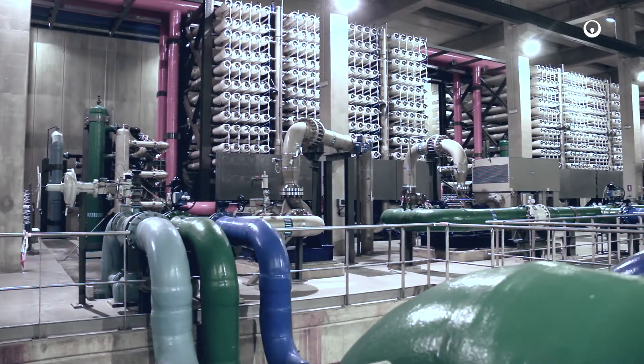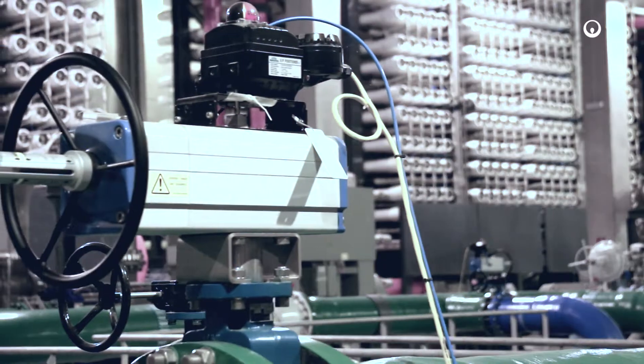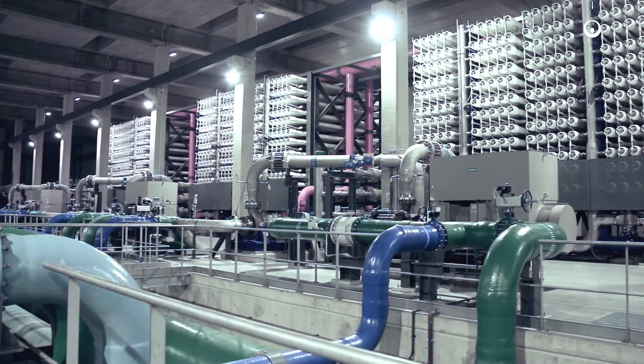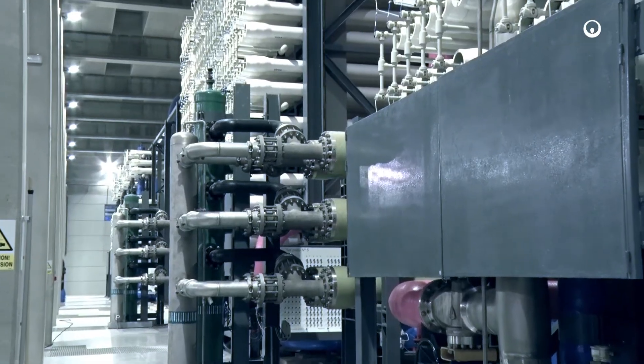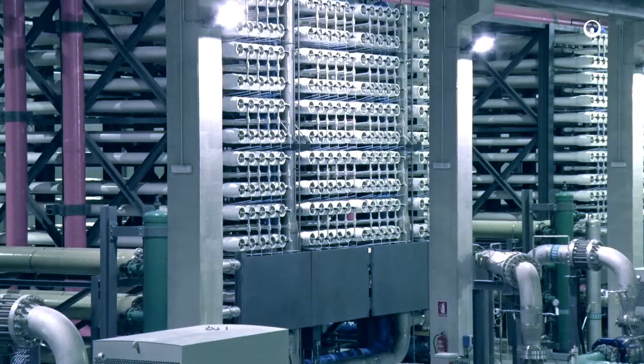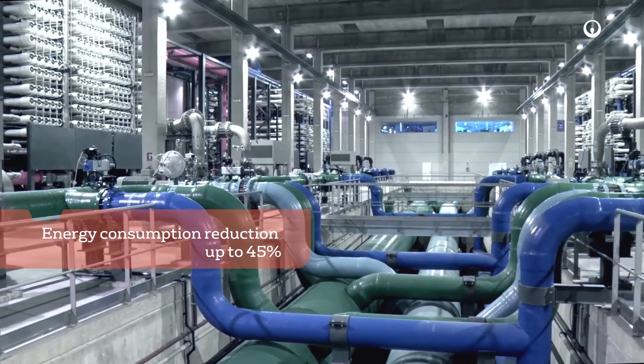Reverse osmosis is the heart of the process. The facility is designed with two reverse osmosis passes. The first comprises six production trains and features a DWEER pressure exchanger with an efficiency of over 95%, which enables energy consumption in reverse osmosis to be reduced by up to 45%.